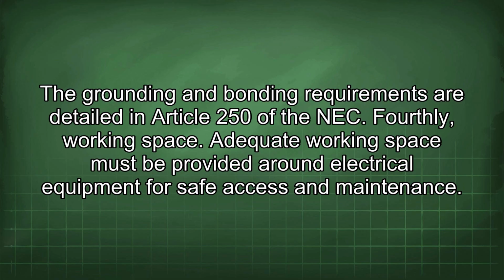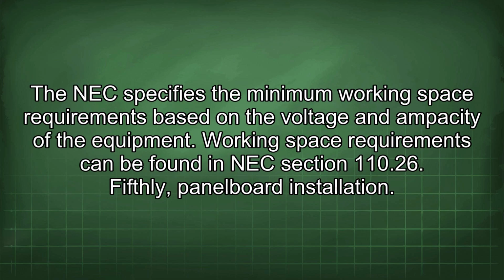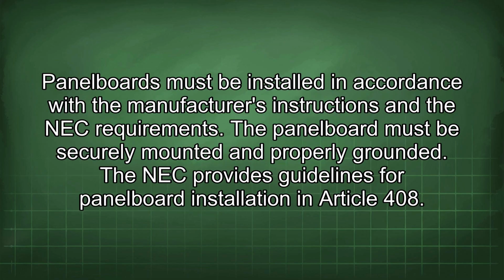Fourthly, working space. Adequate working space must be provided around electrical equipment for safe access and maintenance. The NEC specifies the minimum working space requirements based on the voltage and ampacity of the equipment. Working space requirements can be found in NEC section 110.26. Fifthly, panel board installation. Panel boards must be installed in accordance with the manufacturer's instructions and the NEC requirements. The panel board must be securely mounted and properly grounded. The NEC provides guidelines for panel board installation in Article 408.